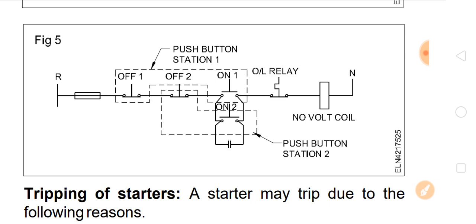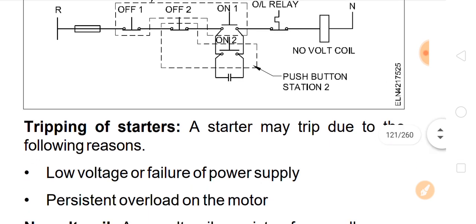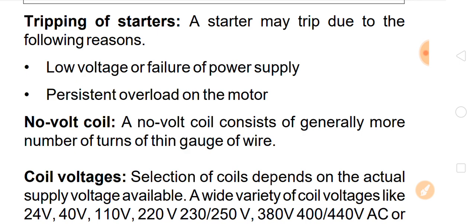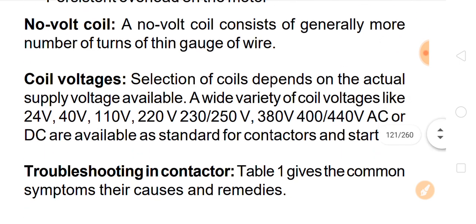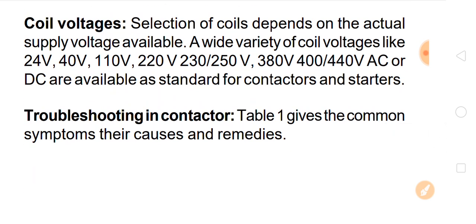Tripping of starters: a starter may trip due to the following reasons — low voltage, failure of power supply, or persistent overload on the motor. No-volt coil: a no-volt coil consists of generally a large number of turns of thin gauge wire. Coil voltage: selection of coil depends on the actual supply voltage available. A wide variety of coil voltages are available as standard for contactors and starters, including 24V, 40V, 110V, 220V, 230V, 250V, 380V, and 440V AC and DC.